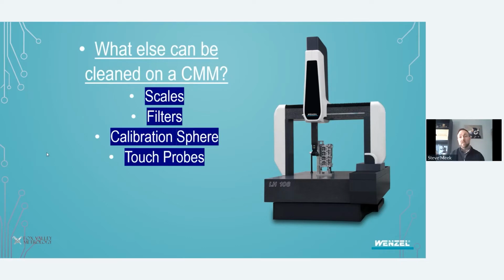Another bad habit we see is, we mentioned denatured alcohol earlier, which is great for some areas. We do not want to use denatured alcohol on scales. This will actually remove the lacquer right from the scale, which presents other challenges and usually requires a scale replacement. Instead, the proper method for scales is to use isopropyl alcohol, preferably at 90% or higher, with a non-abrasive wipe. Lint-free terry cloth, something like that would work fine. But equally as important to what you use is how we're actually using it. The cleaning method for these is critical.